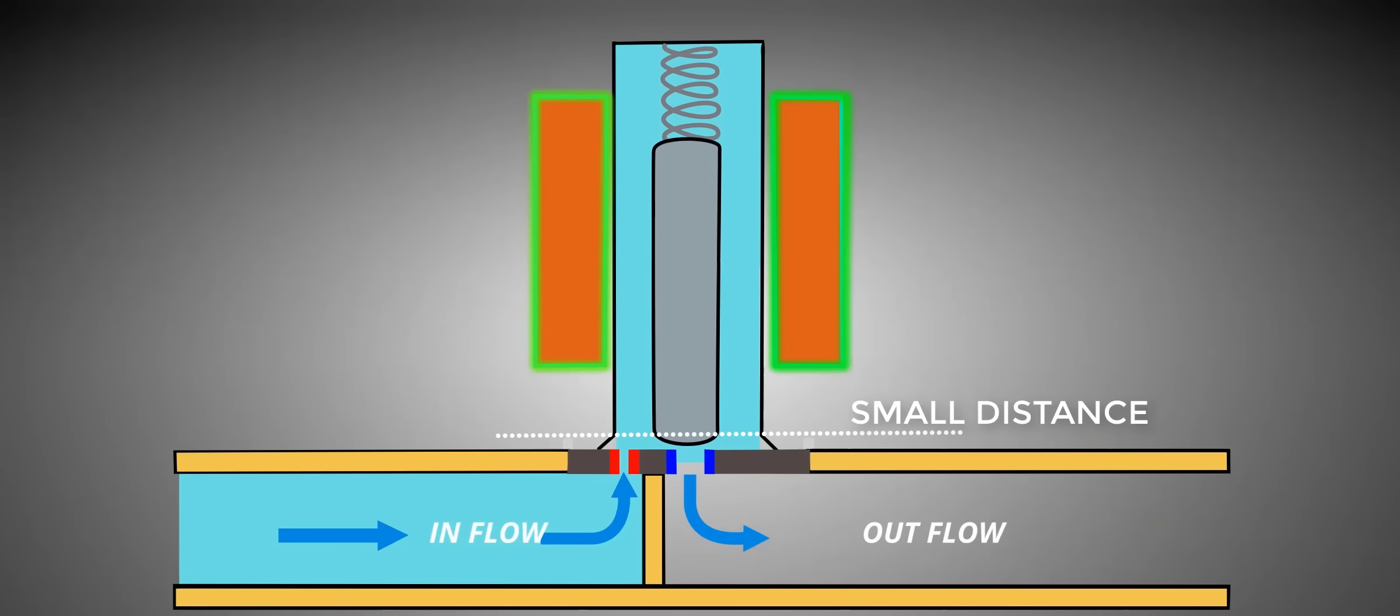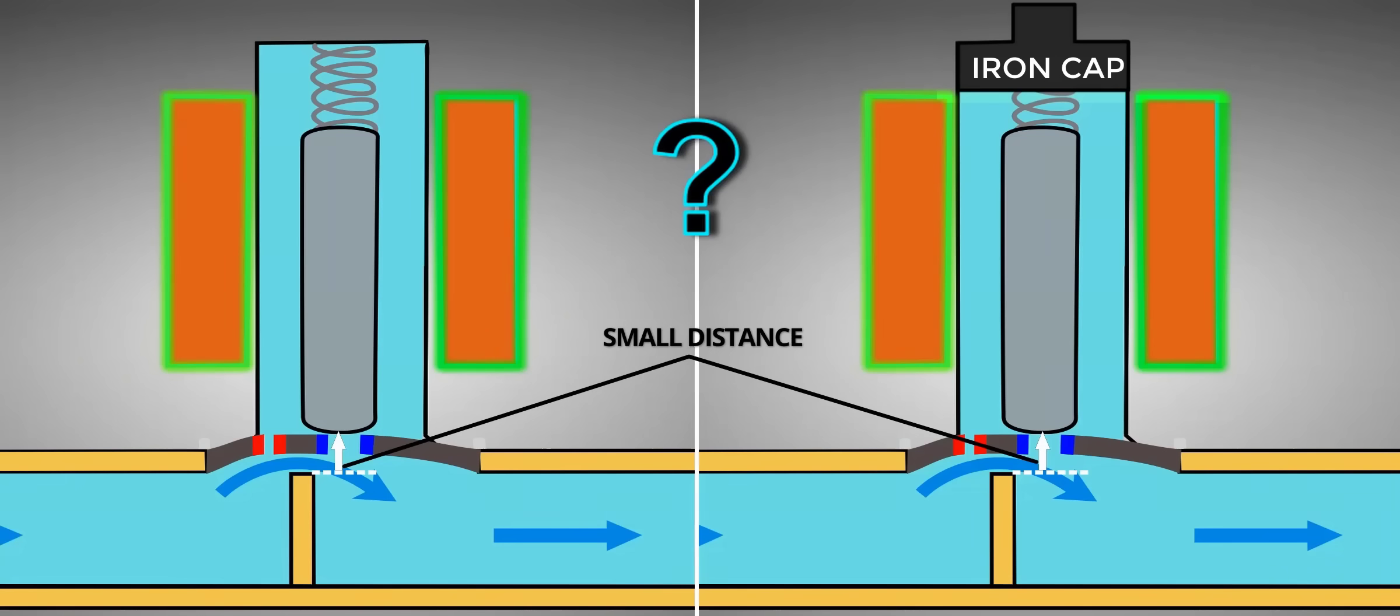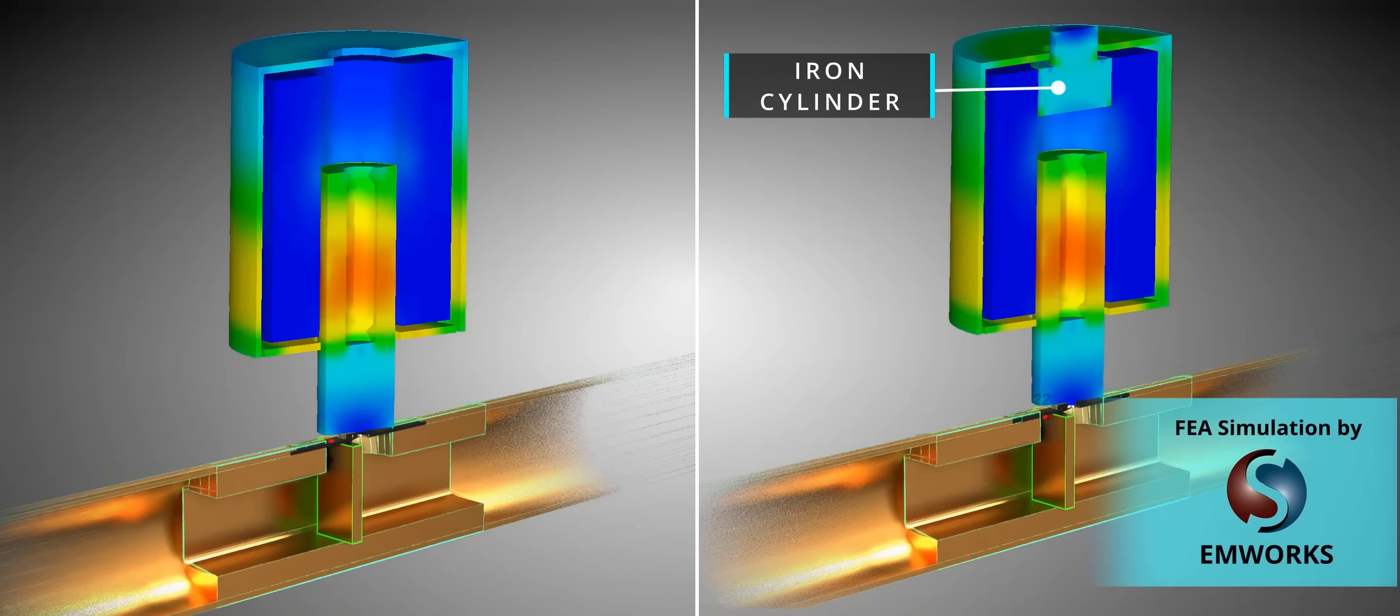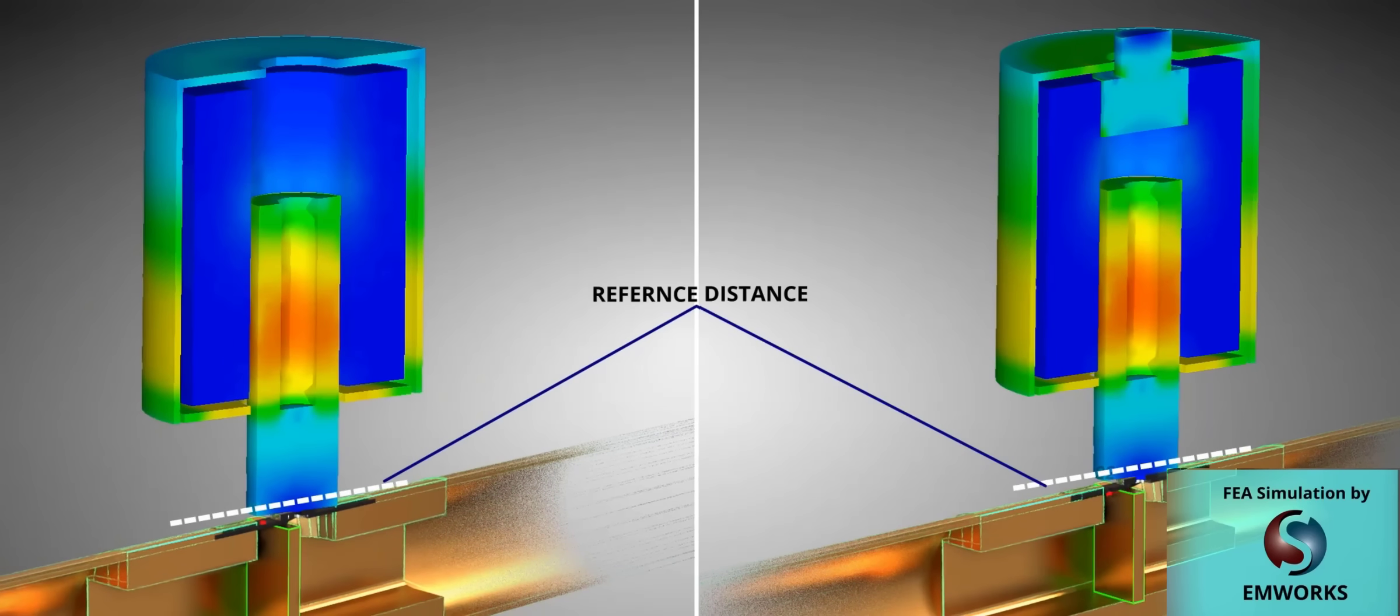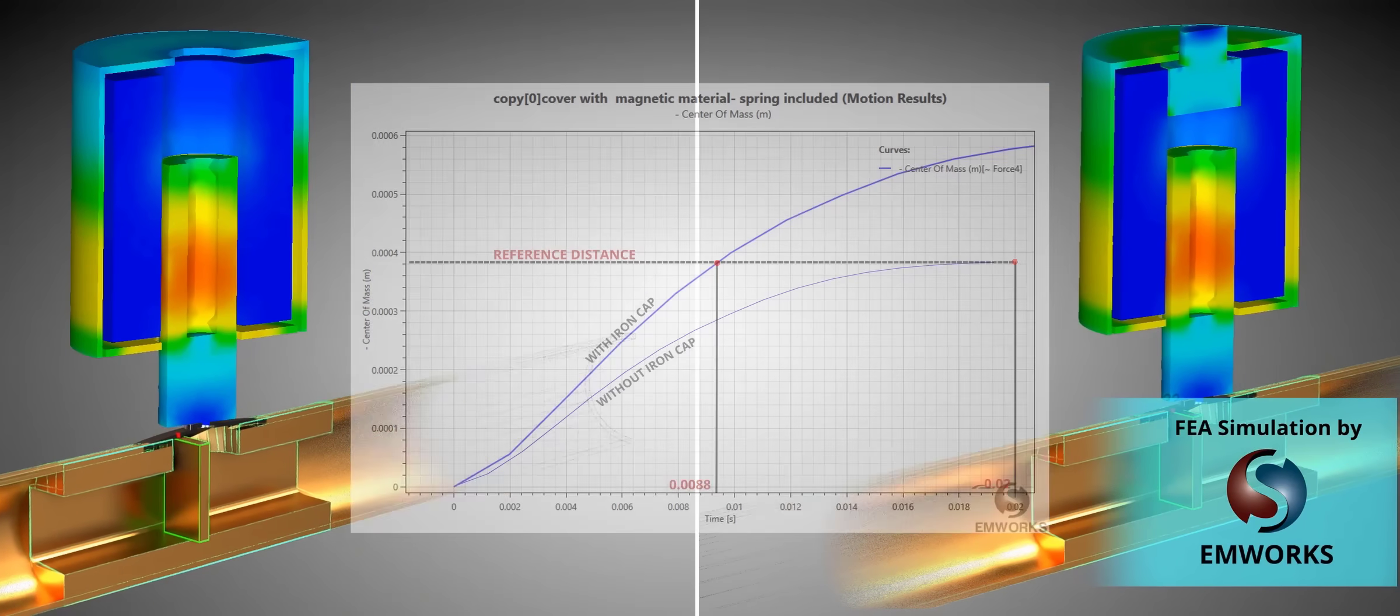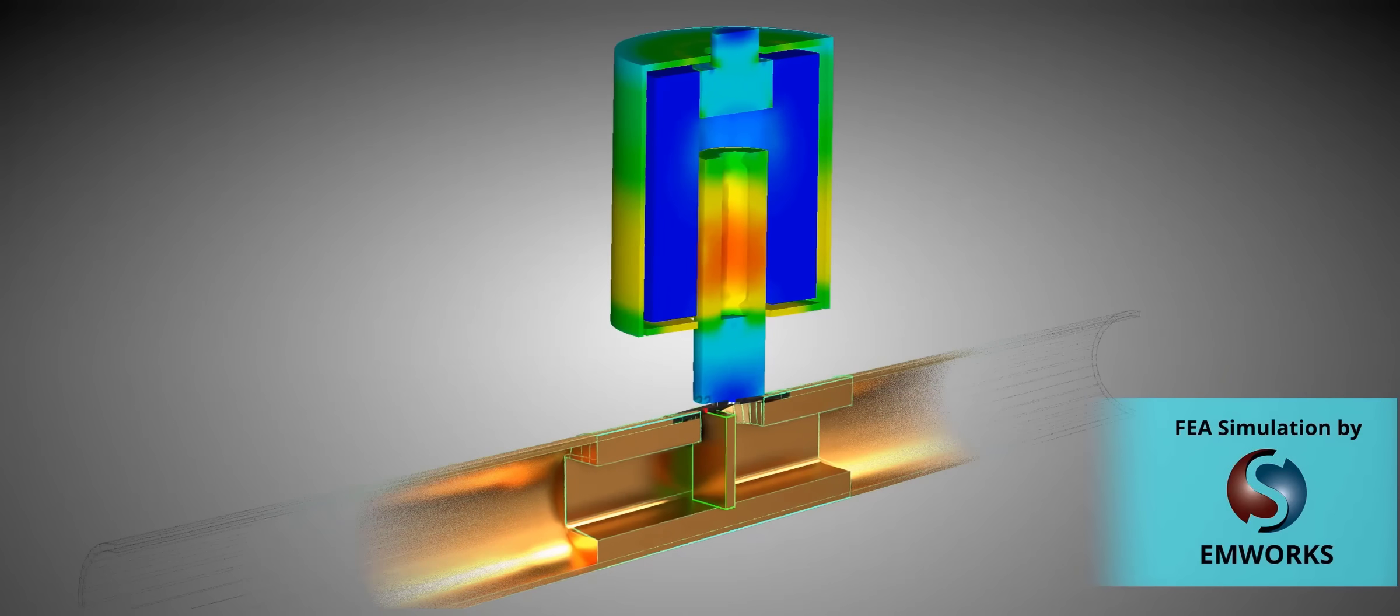We already learned that after the armature has moved a small distance, the diaphragm bends and the valve becomes operational. Now, let's see which design achieves that small distance first. Here is a competition between a solenoid valve with and without this iron cylinder, using the popular FEA simulation software EMWorks. You can see that the solenoid valve with the extra iron cap reaches that distance in half the time of the other case. This obviously reduces the response time of the solenoid valve. The reason for the fast movement is that the iron cap produces a strong magnetic pole. There you have it. We have now designed a quick and efficient 2x2 solenoid valve.